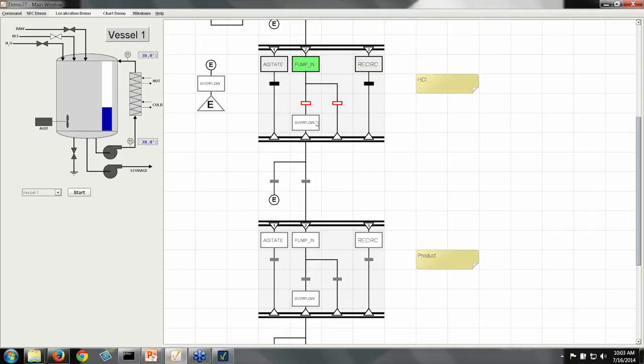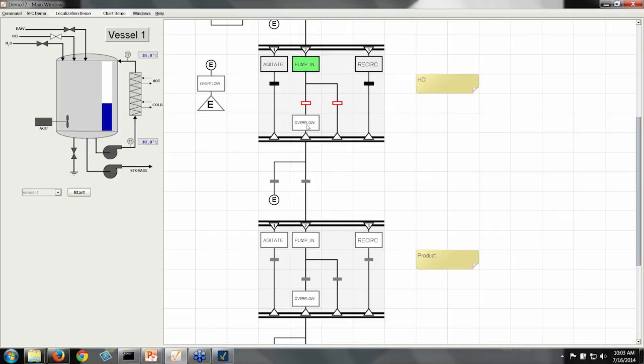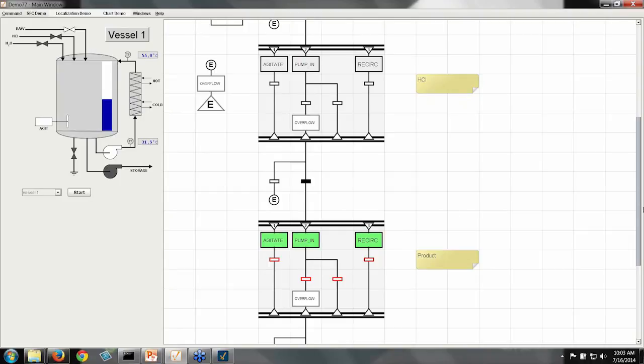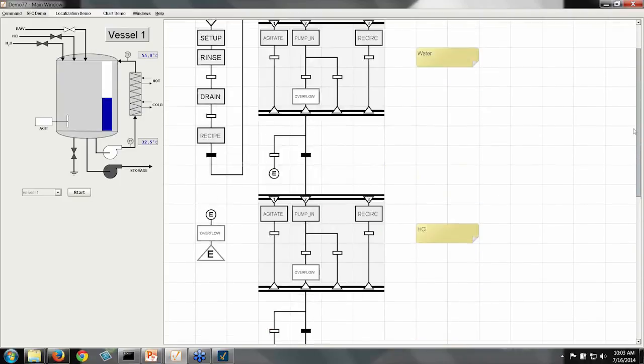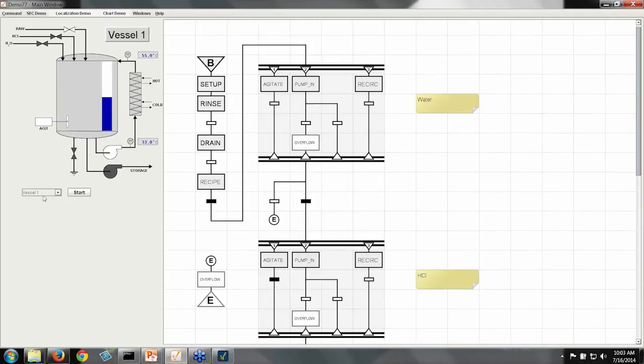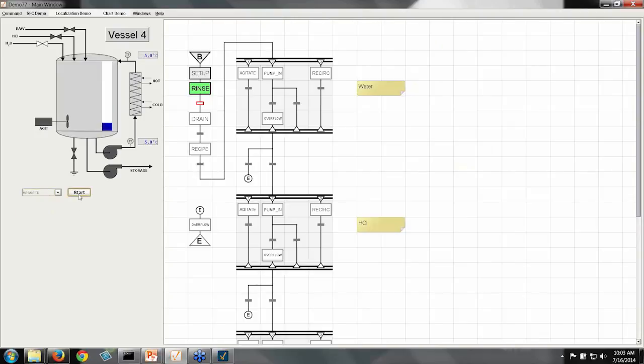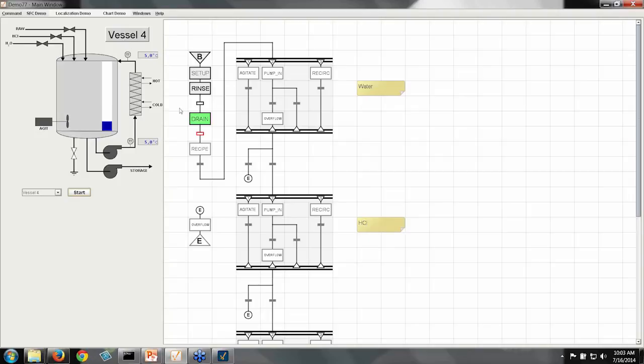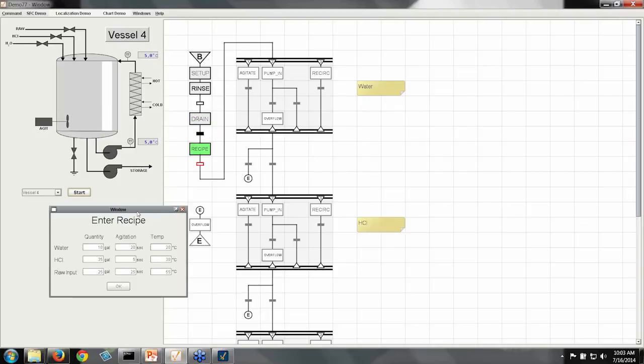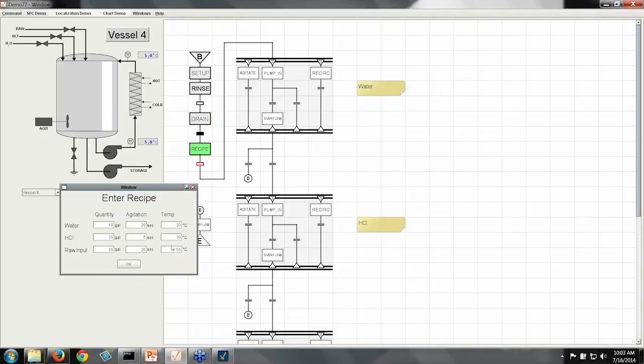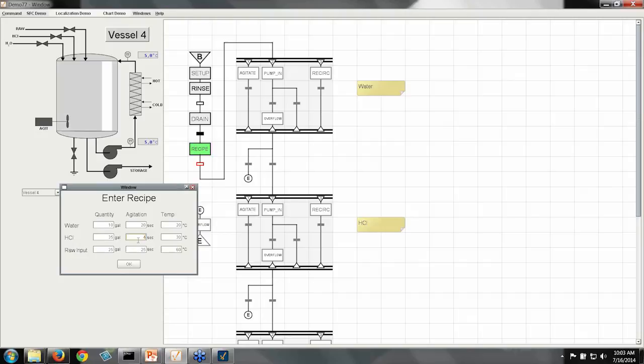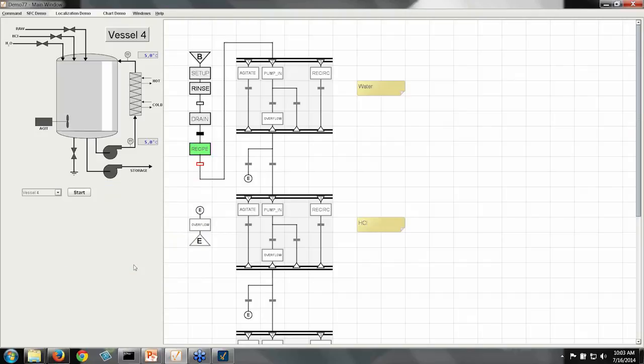And you can see that this chart is just going to follow this logic all the way down, where each piece of this logic has been altered by the recipe that I chose. So the amount of time and the temperatures that I'm requiring are all governed by the recipe that I fed to the chart. And I've got some error checking here, where if I ever pump in too much stuff, I'm going to stop pumping in and I'm going to overflow, which brings me to this error handler over here. Now, this is all nice, but the real power here is that I've got six vessels. So I could go over here to vessel four, and I could start vessel four's batch.